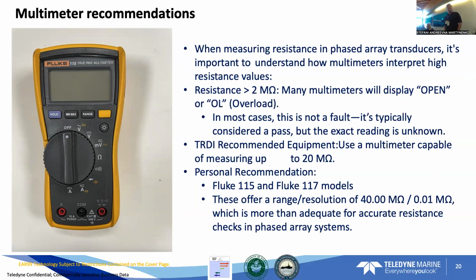So I recommend that you use a meter that goes up to at least 20 megohms. I personally recommend the Fluke 115 and 117 models. I've been using those for years, and they're very reliable. They offer a range of resolution between 40 megohms to 0.01 megohm, which is more than adequate for accurate resistances. I actually had somebody send a resistance check not long ago with one of the lower meters, and I couldn't really tell anything about the resistance check because everything was open. And to me, that's like, uh-oh, I mean, when is an open ever good, right?